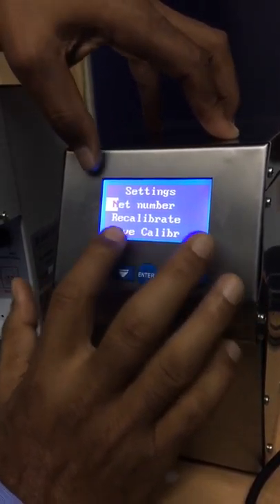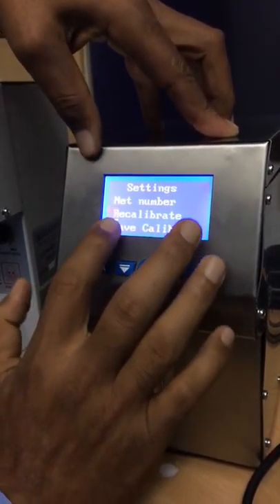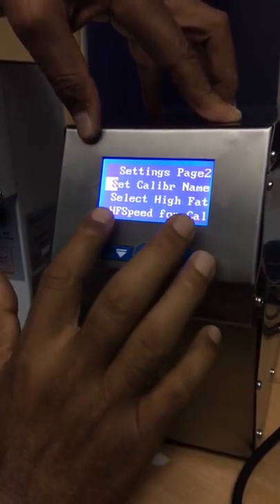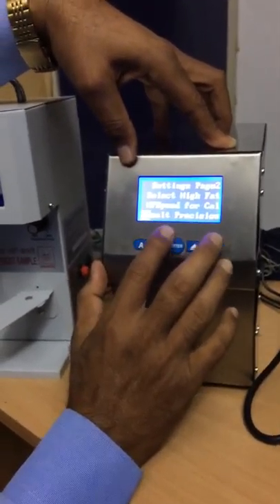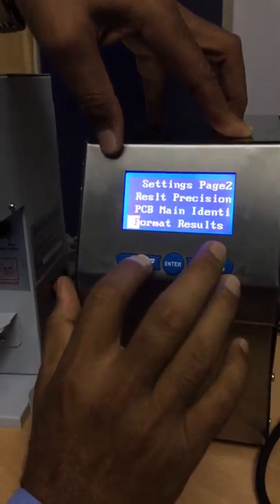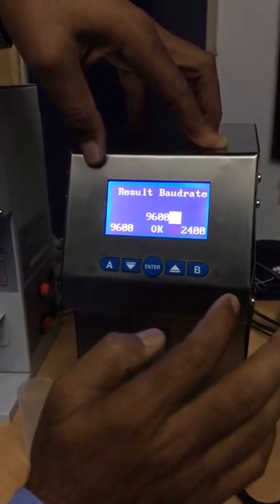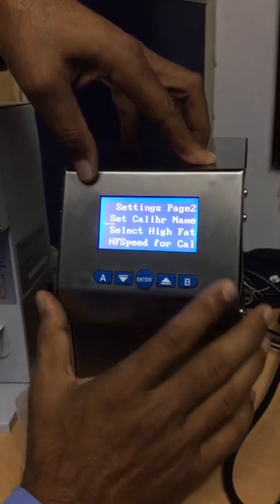In the Settings menu: Net Number, Recalibration — you can save the calibration inside the machine. Options to connect to a computer or PC are also there. Restore Calibration — saved calibration can be restored. This is settings page 2: you can name the calibration, select High Fat, set result precision, format result, and set baud rate. When you connect this machine to a PC or DPU you set the baud rate — for example 9600 — and you can change it to 2400 if needed.